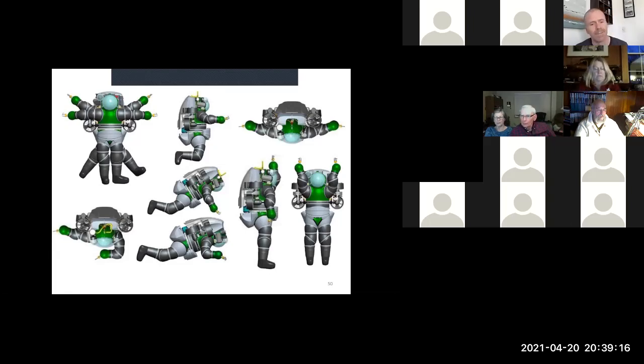No, there is a pressure relief valve set to 1/3 of a PSI, but that pressure relief valve responds to the pressure gradient across the suit. So if the pressure inside the suit is 0.33 PSI greater than the pressure outside, it will crack open and vent. That's really only of practical use on the surface, but it's a rule the governing body has in the specifications.